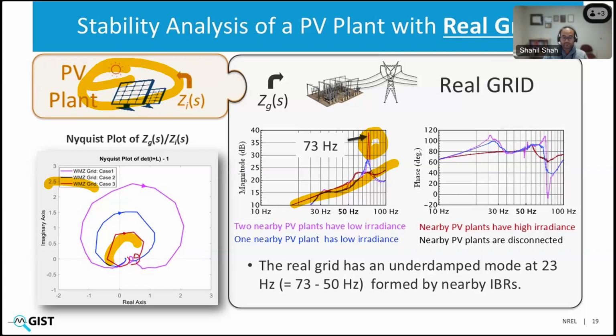When we use this blue case of the grid, the stability reduces because the Nyquist plot gets closer to the critical point. And then when we use the pink trace, it encircles the critical point, showing that the grid and the plant become unstable. So that really shows how grid and IBR together, how we can do mix and match to understand stability.